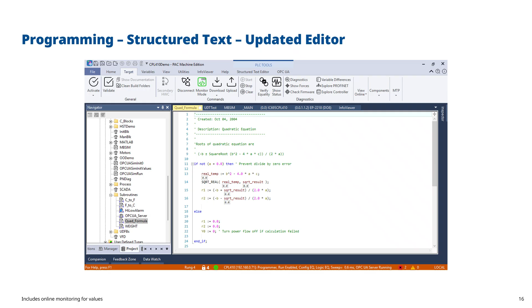So a very good way of finding out what the evolution of the application is, because that appears inside the structured text editor. And we have updated this editor recently, so it's also got color coding. So the different colors indicate different things. So green is a comment. You've got blue for instructions and functions. You've got black for things like built-in PLC functions like square root. And then a sort of reddy brown color indicates a variable. And then you've also got a slightly different greener color, which is used for parameters, because this is a parameterized subroutine block.